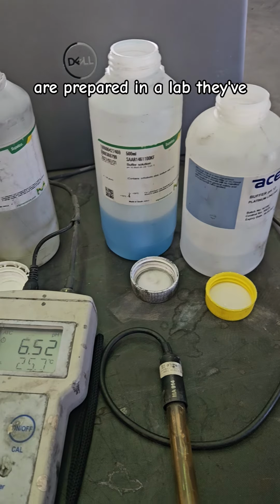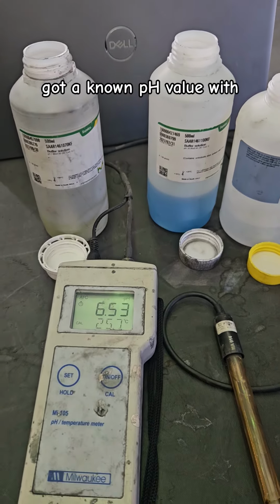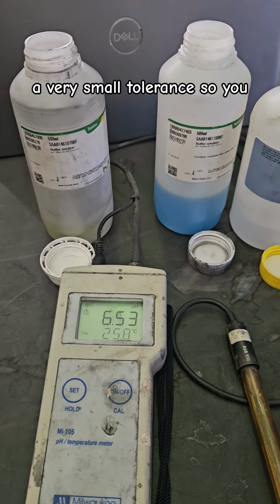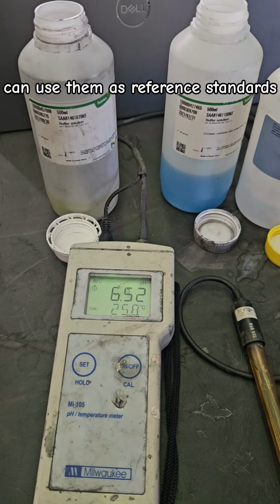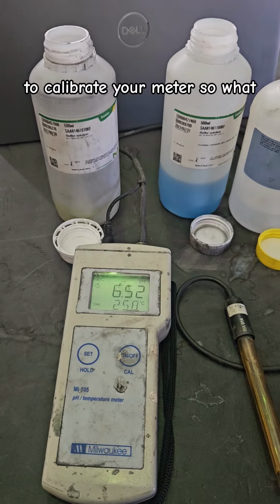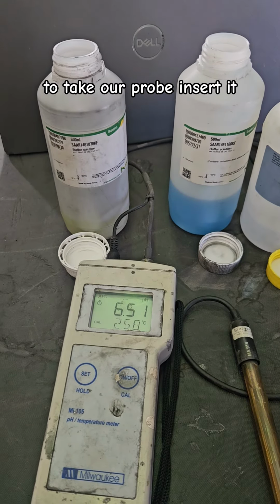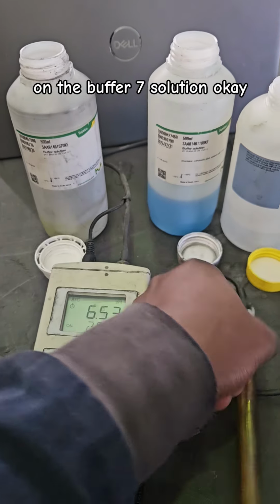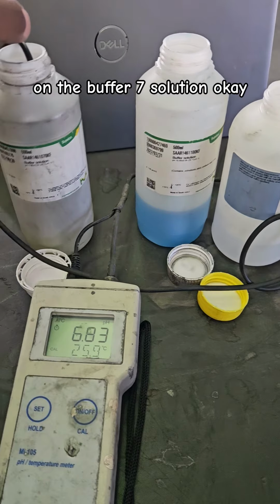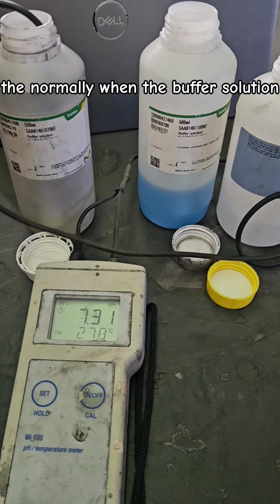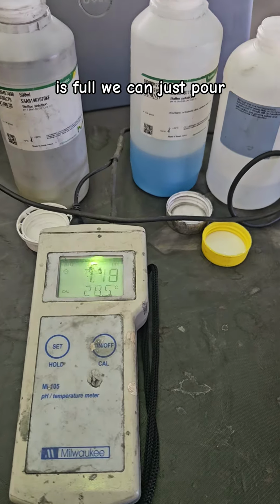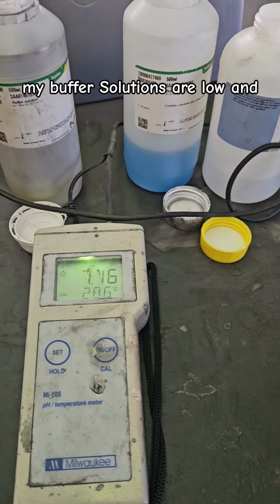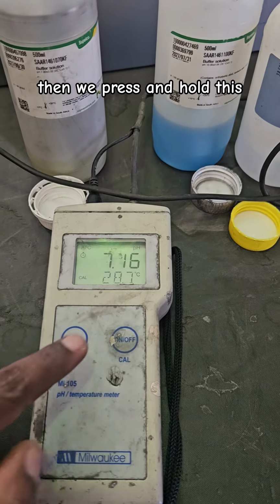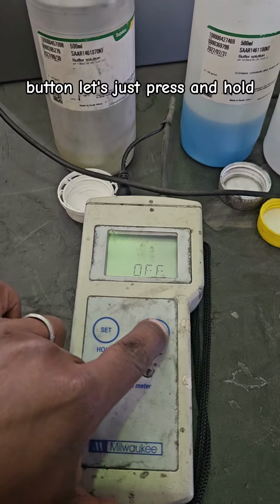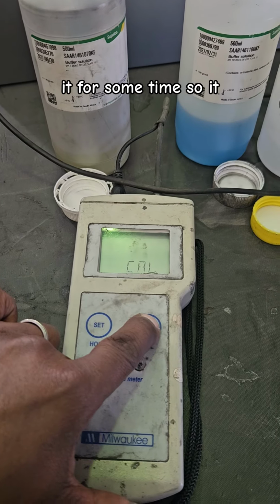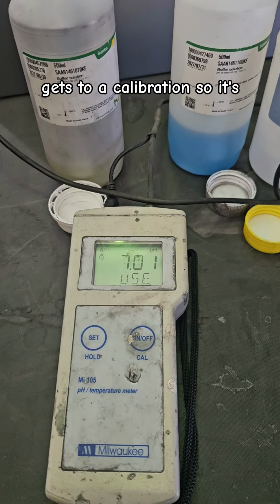They are prepared in a lab. They've got a known pH value with a very small tolerance, so you can use them as reference standards to calibrate your meter. So what we're going to do, we're going to take our probe, insert it in the buffer 7 solution. Okay, insert it all the way to the bottom. Normally when the buffer solution is full, we can just pour it into a beaker, but now my buffer solutions are low. And then we press and hold this button. Let's just press and hold it for some time so it gets to a calibration.